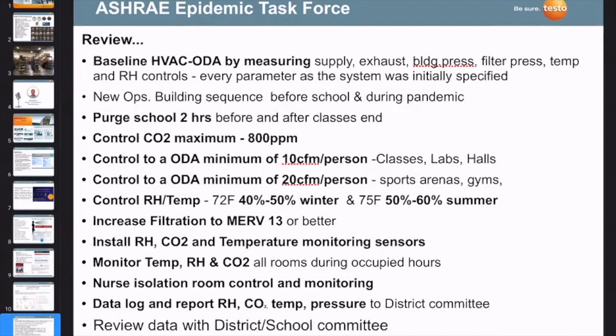Going forward from that, the operational sequence, once schools open back up, is that you must purge that school for 2 hours before class and 2 hours after class with max exhaust air, max supply air, max outdoor air, basically a complete purge and a wash of that building. On top of that, during the school operational hours, control and maintain a minimum outdoor air volume of 10 CFM per person. That is in all common classroom areas, labs, hallways.